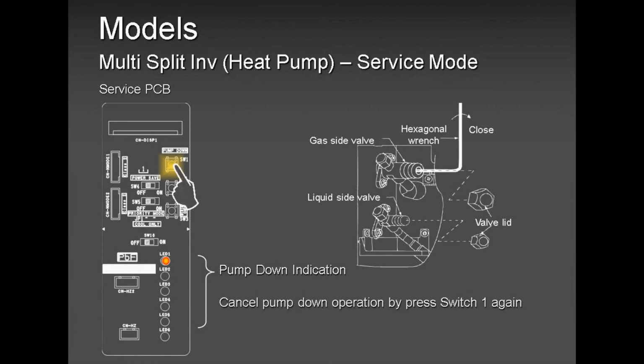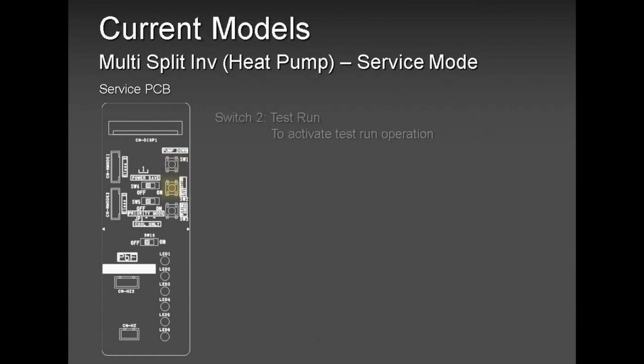Unlike the single zone, the multi-zone has a card. When you open up the control panel, there is a small card on the left-hand side. We call it a service PCB, and what it has, you will see right now. One of the buttons is a pump down. Everybody knows what a pump down is. Basically, what is a pump down? It collects all the refrigerant back into the outdoor unit.